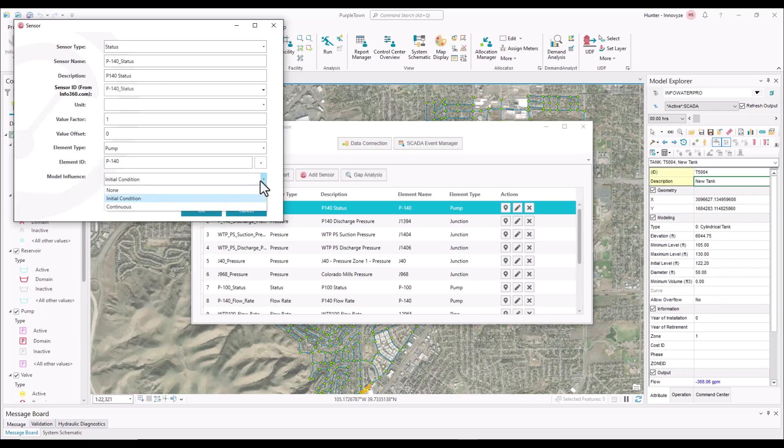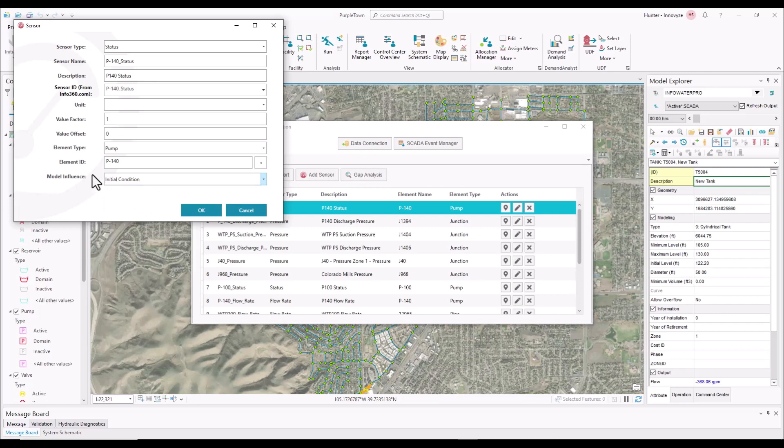You can have none where it will have no influence on the model. I can set it to initial conditions where InfoWater Pro is going to use that sensor just for the initial condition and then run as normal. And then you can also have continuous where it is going to try and map as close as possible. So for this one, we're just going to start from initial condition, but this is how you can really see some of the bridges between Info360 Insight and InfoWater Pro.